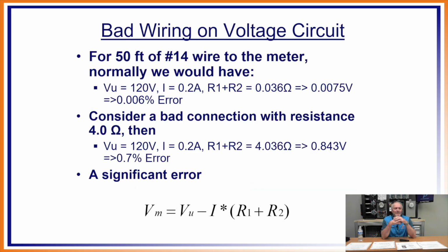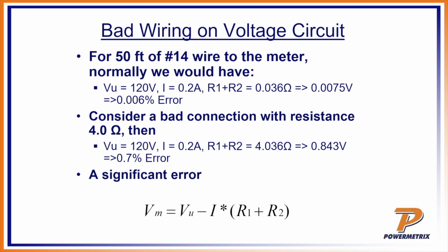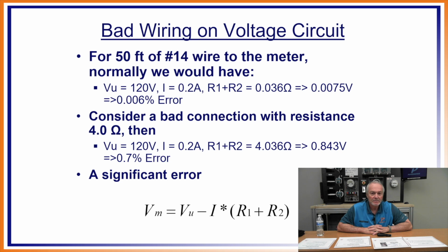For 50 feet of number 14, you can see the formula down at the very bottom of the screen. We're looking at the voltage there at the meter. So you've got 120 volts, and you've got a current of 0.2 amps, and I've got resistance there in the back of 0.036 ohms. That comes up with 0.006% error. So no one should be upset about that.